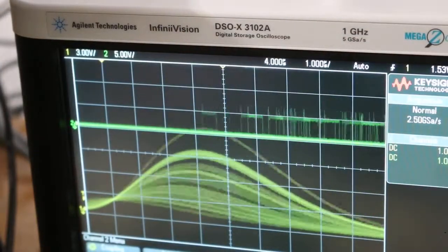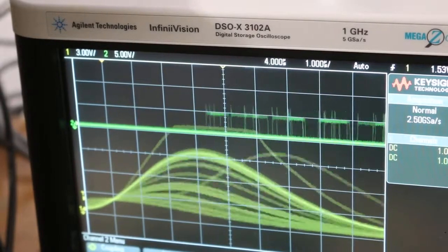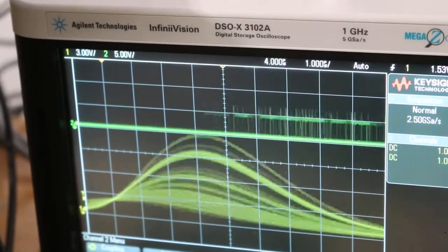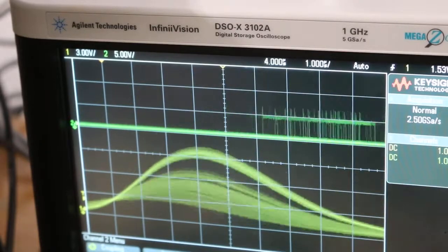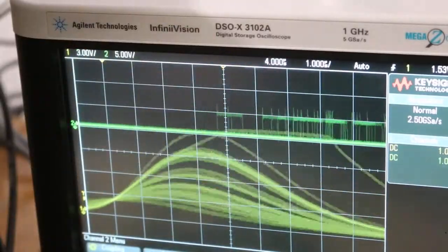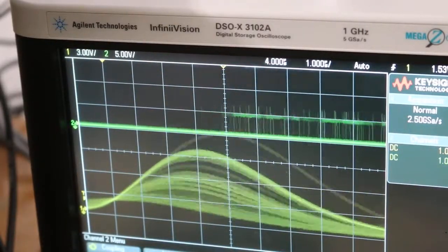Now those pulses are square pulses, known in electronics as TTL pulses that go between 0 and 5 volts. And that is the SCA's reaction. So the way the SCA reacts to a voltage coming in is if the voltage is within the window that we set, the SCA will send out a pulse. If it's not within the window, it won't do anything.